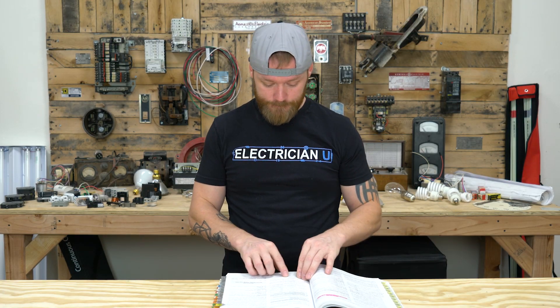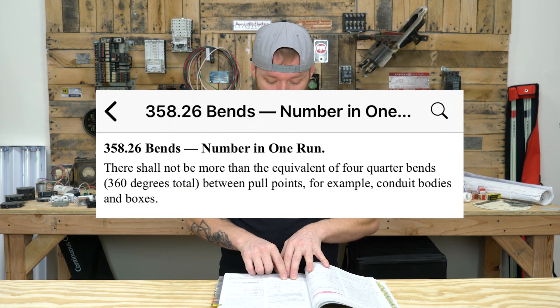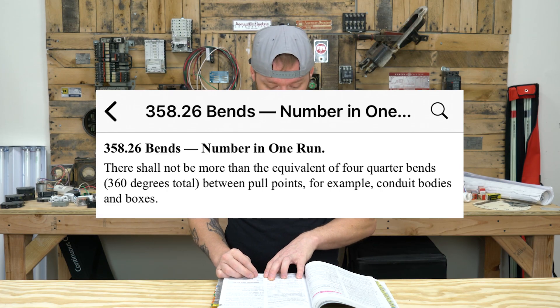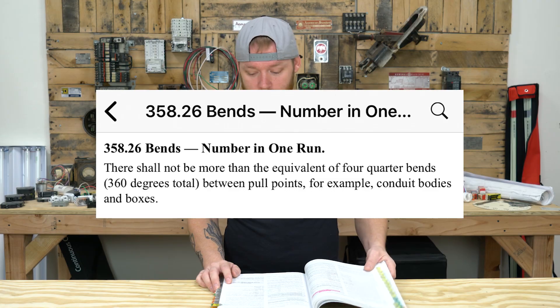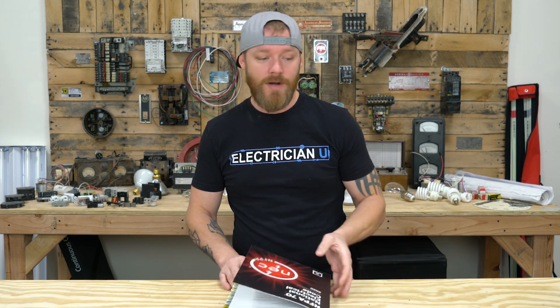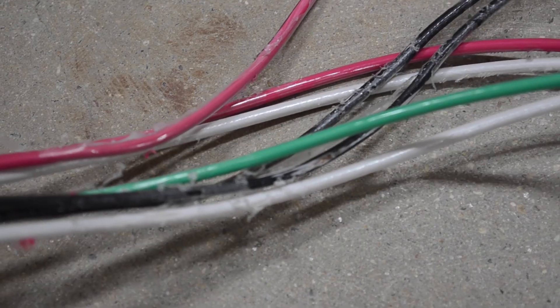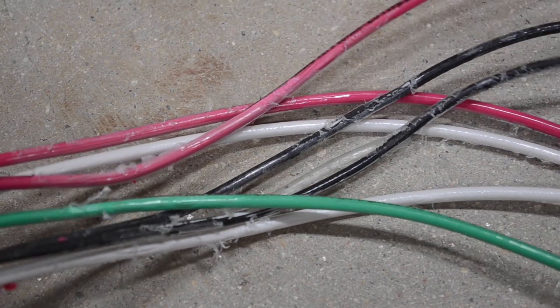It just says bends — number in one run: there shall not be more than the equivalent of four quarter bends, or 360 degrees total, between pull points — for example, conduit bodies and boxes. That's really what they're trying to do: limit you. It doesn't have any other reason other than damaging insulation. If you're trying to yank conductors through a pipe, you're going to damage the insulation. That is why the NEC puts that in there as a maximum.